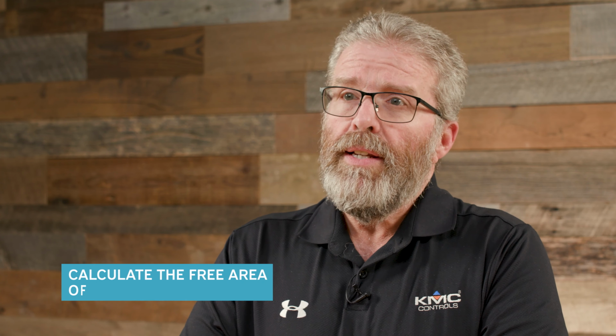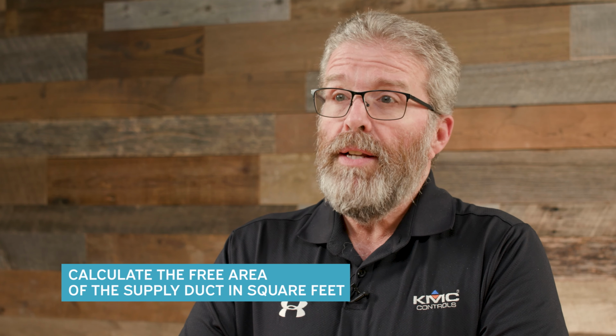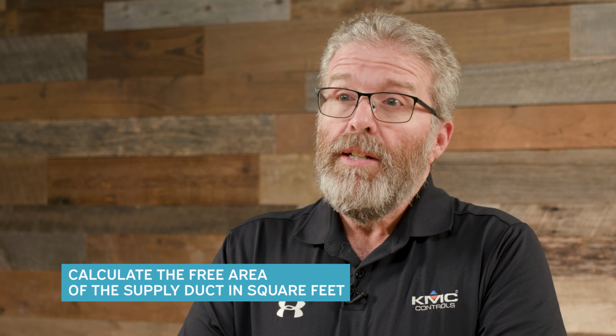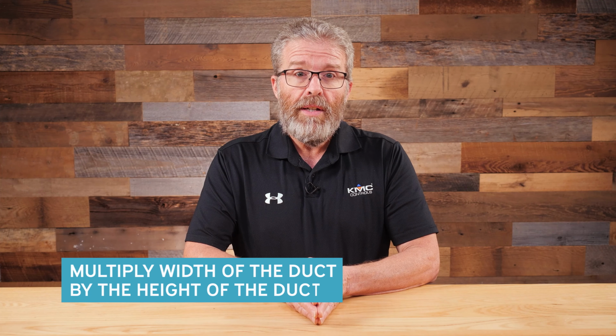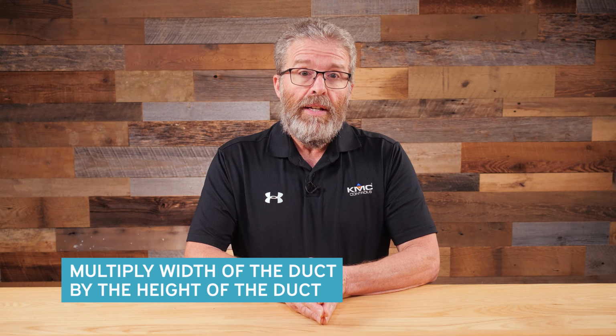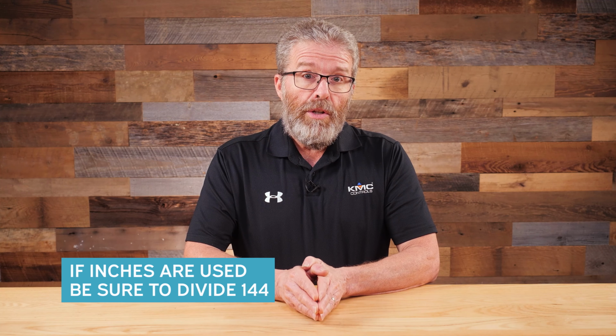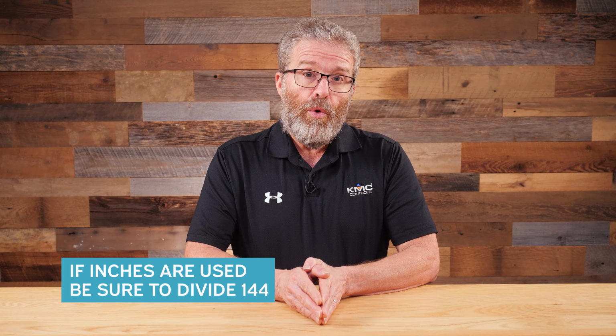Now that everything is installed, I need to measure the supply duct at the cross section where the pitot tubes are installed and calculate the free area of the supply duct in square feet. The calculation used for this is to multiply the width of the duct by the height of the duct. If inches are used, be sure to divide by 144 to get your square feet. Save this result for the commissioning stage.